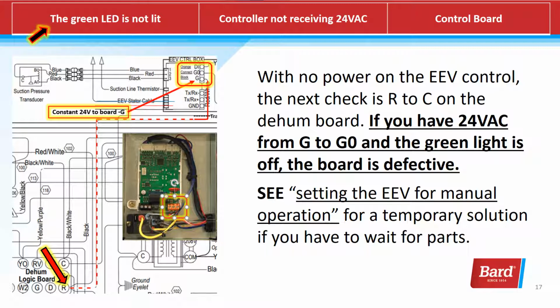With no power on the EEV control, the next check is R to C on the dehum board. And you can see in the lower left corner, I have a big red arrow there pointing to R, and the white and red dotted line goes from G. That's where we get our 24 volts for the board. The board is powered all the time. If we have 24 volts from G to G0 and the green light is off, the board is defective. If the board is defective, we need to set up the EEV for manual operation, and we'll learn how to do that a little farther into this video.